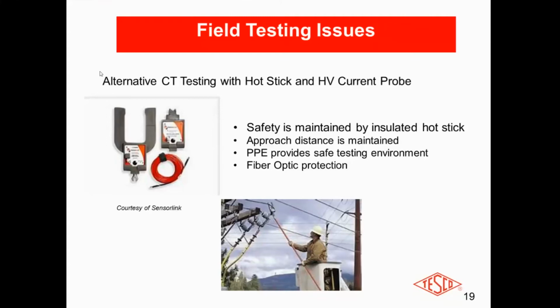The benefit to using this, of course, is you are nowhere close to the actual cables and probes yourself. As you can see in this picture, I've got this journeyman lineman in a bucket truck. Now, this particular test has been done on an overhead service, which again is very common. Unfortunately I didn't have a photograph to share with you, but if you can imagine the same situation, where you're holding that hot stick, you have a fiber optic cable, which is that little orange cable you see in the picture on the left, which will go from the actual hot stick, which is the U-shaped clamp, come down into that little sensing unit, which is on the base, and then that sensing unit will go to the measurement equipment.